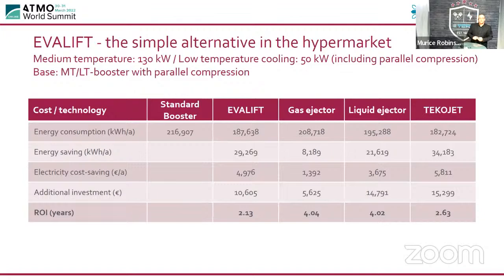So having a look at a 130 kilowatt system, medium temperature, and 50 kilowatts on low temperature, and including parallel compression on these ones. So we had a standard booster system. Kilowatt hours per year was 216,000. EVALIFT was 187,000. Gas ejector 208. Liquid ejector 195. And including EVALIFT and TEKO Jet, we got to 182. So the TEKO Jet and EVALIFT was obviously the winner.